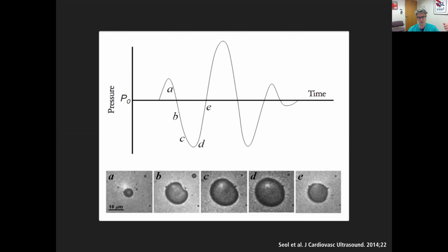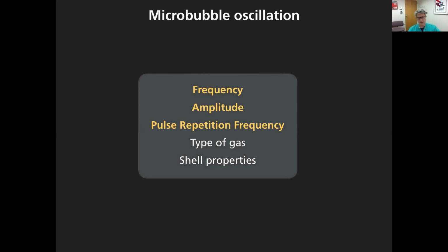Here, under a microscope, you can see in the pressure wave, it contracts, expands and collapses. And the microbubble oscillation is dependent on a couple of factors. Three of them you actually have some control over with your machine, which are the frequency, the amplitude, and the PRF, the pulse repetition frequency. The type of gas and the shell properties are not under your control. But with the first three, you can actually enhance and optimize your image.